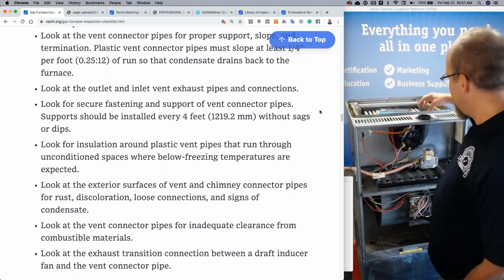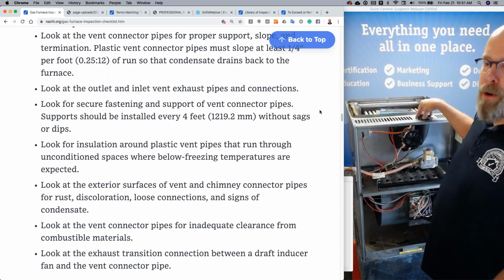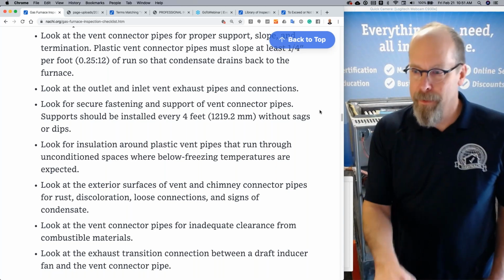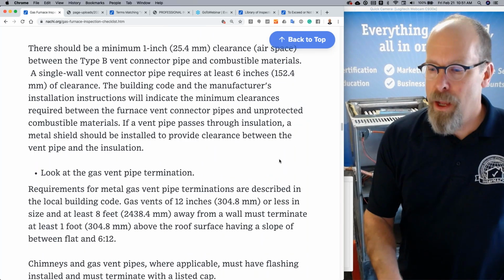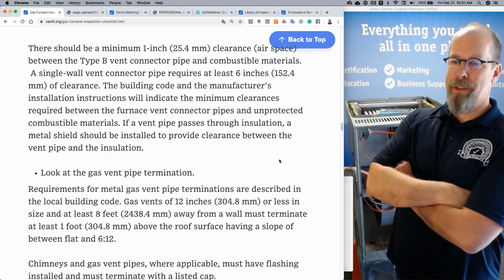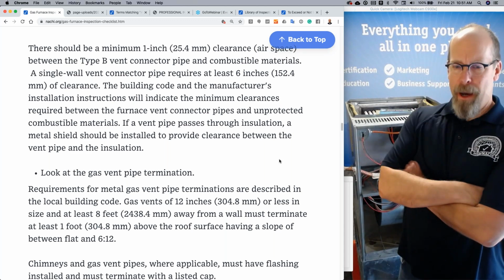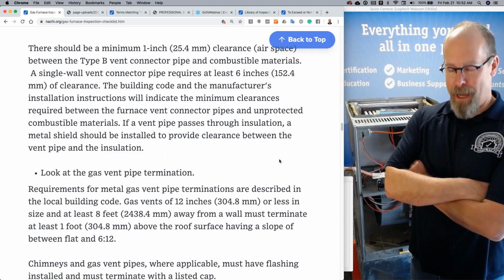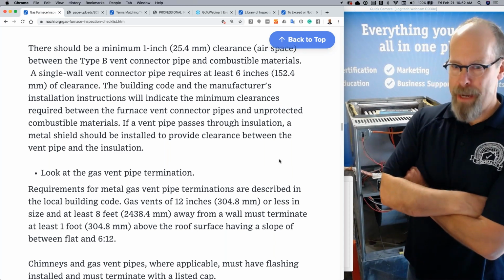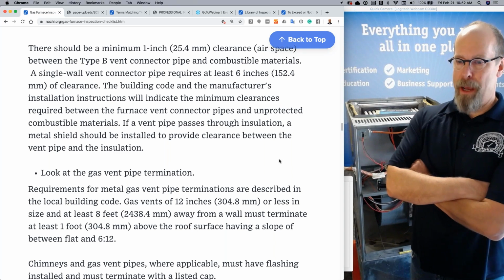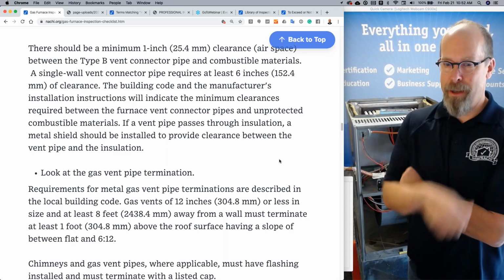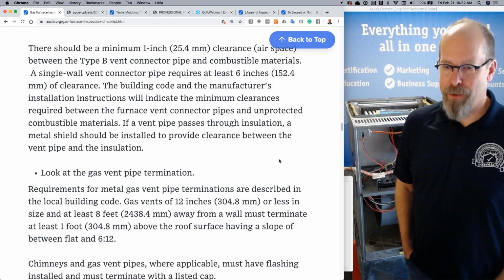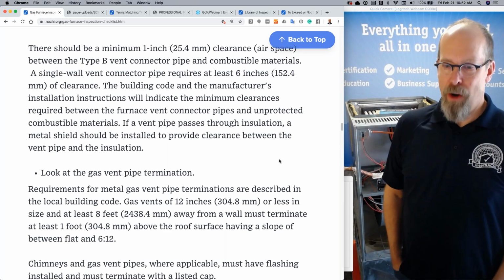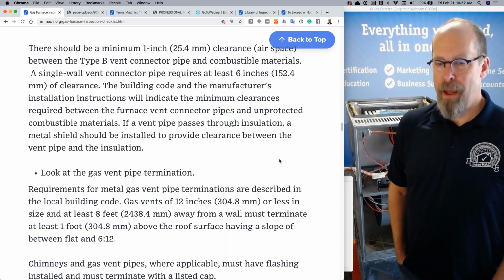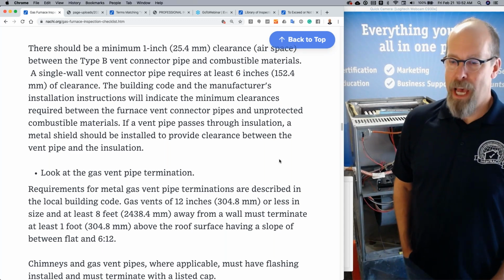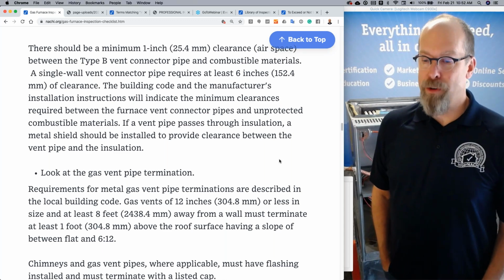So apparently in the past, this connection has been poorly installed and poorly connected. So you need to get that. But take a look at that. Just look at it. Clearance. There should be a minimum 1 inch clearance, 25.4 millimeters of airspace, between the type B vent connector pipe and combustible materials. A single wall vent connector pipe requires 6 inches because it's hot, you can't even touch it. The building code and manufacturer's installation instructions will indicate the minimum clearances required between the furnace vent connector pipe and the combustible materials that are not protected. If a vent pipe passes through insulation, a metal shield is needed.